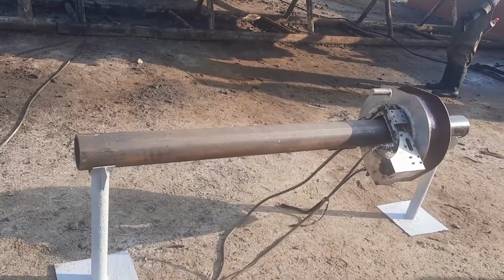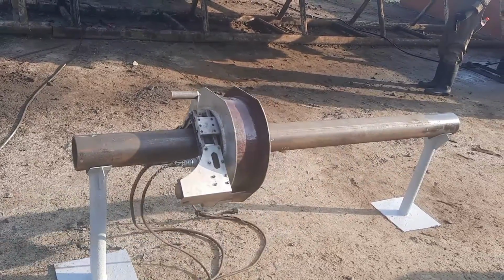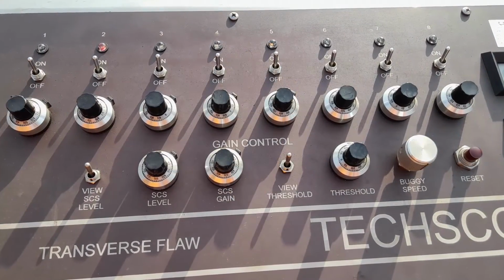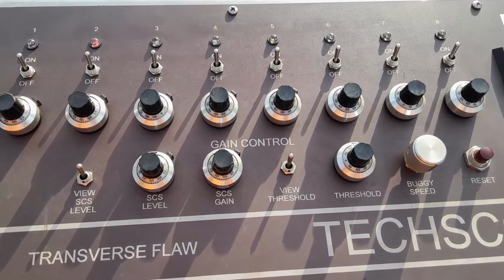Then to adjust the speed, select the speed at which you can easily run it on the calibration block, and move the buggy forward and backward. Then the buggy is okay. Right now your buggy head, coil and drive, everything is working because it can move forward and reverse on the calibration block. Next is transverse flaw adjustment.